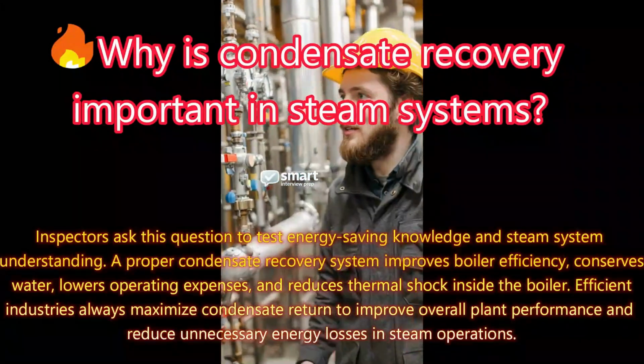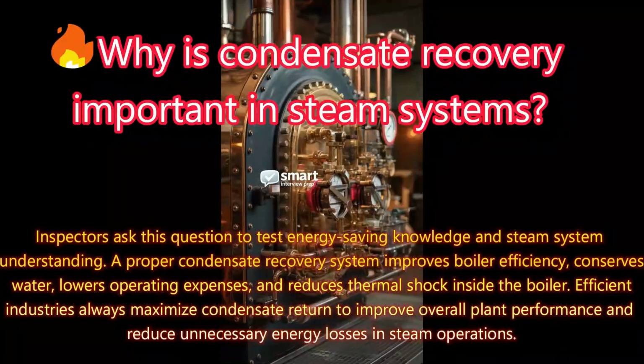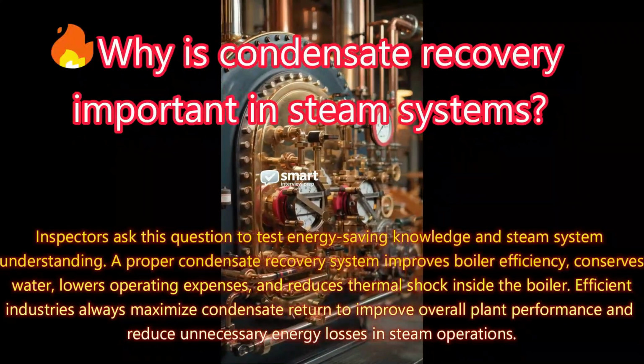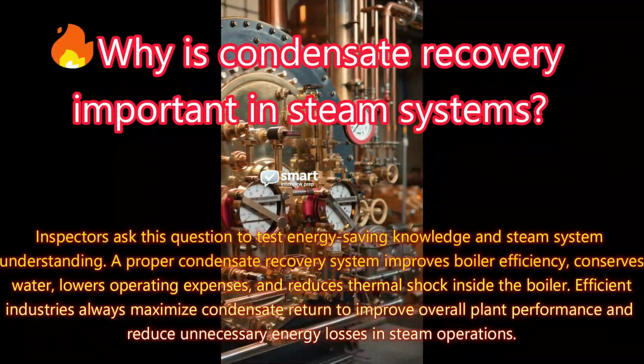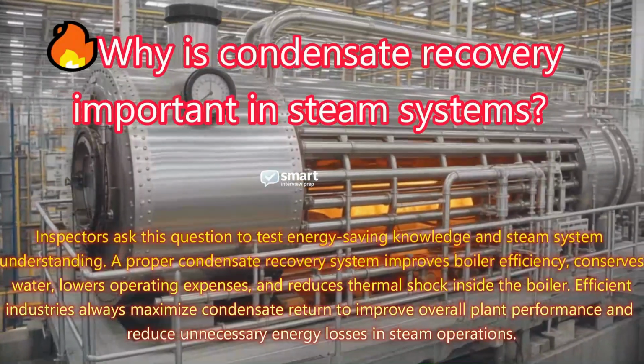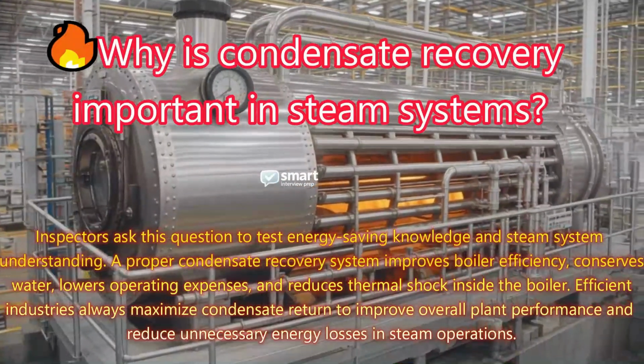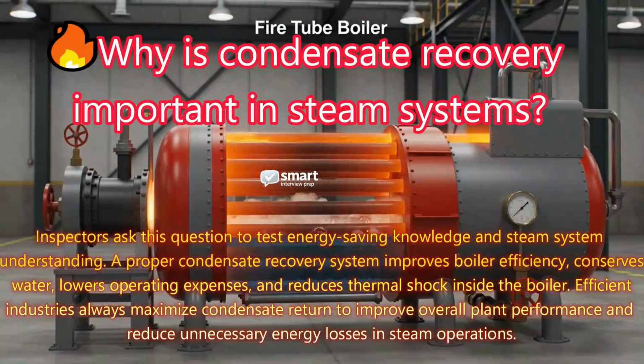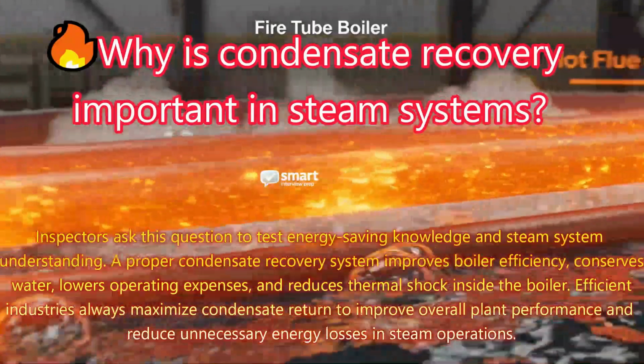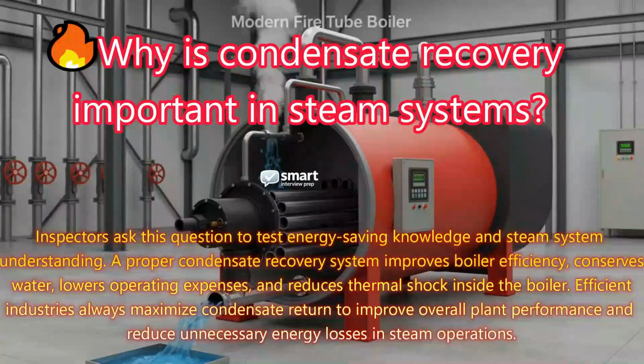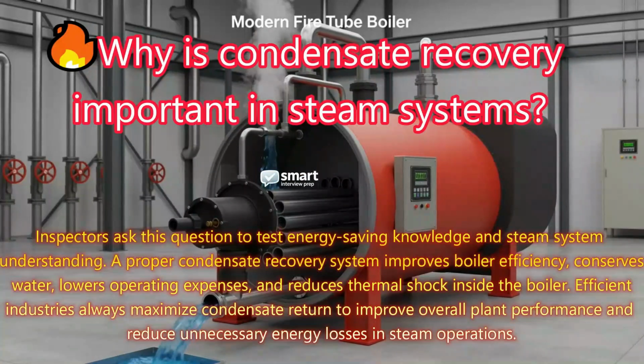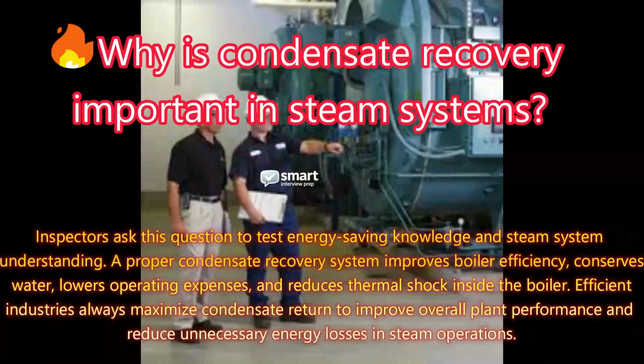Inspectors ask this question to test energy-saving knowledge and steam system understanding. A proper condensate recovery system improves boiler efficiency, conserves water, lowers operating expenses, and reduces thermal shock inside the boiler. Efficient industries always maximize condensate return to improve overall plant performance and reduce unnecessary energy losses in steam operations.